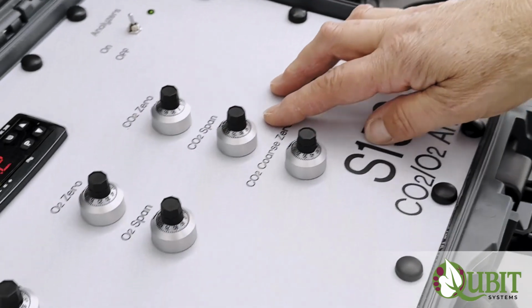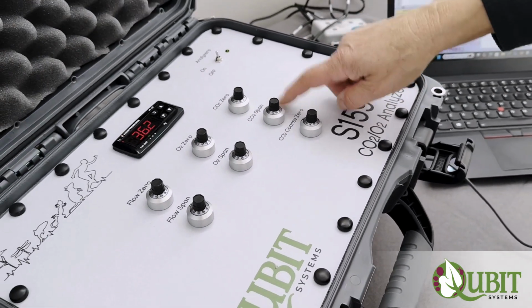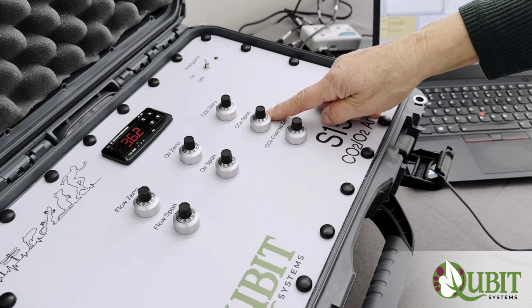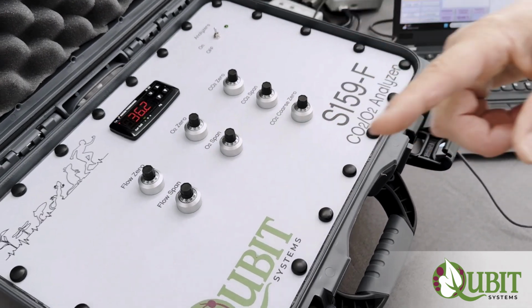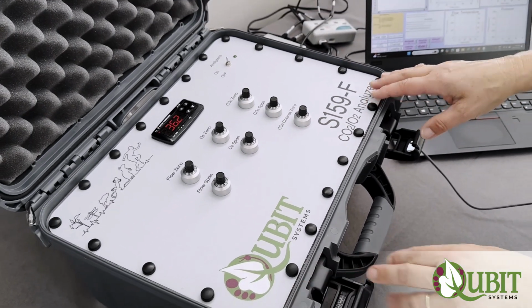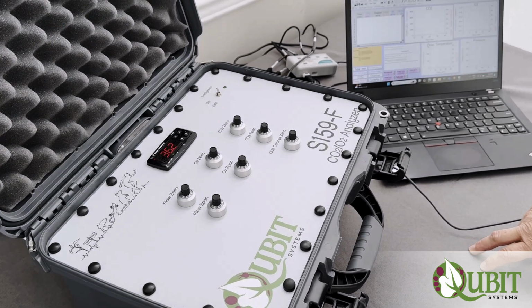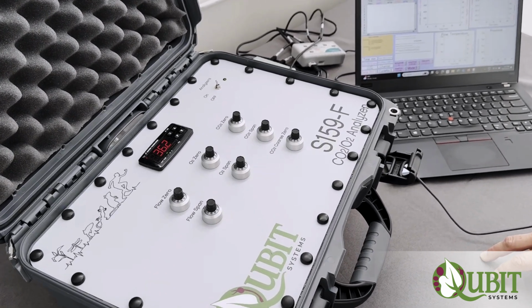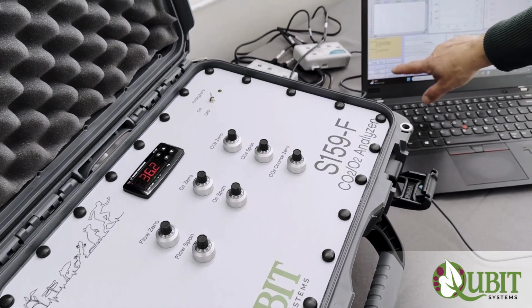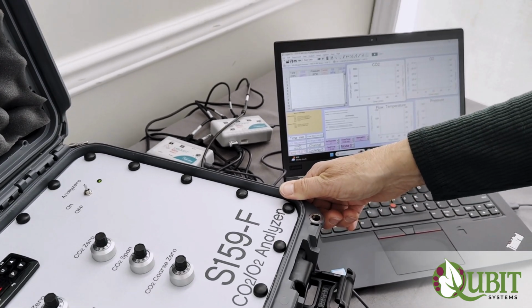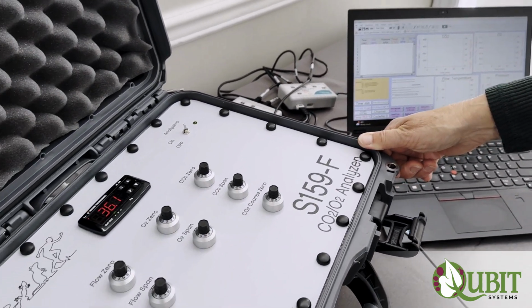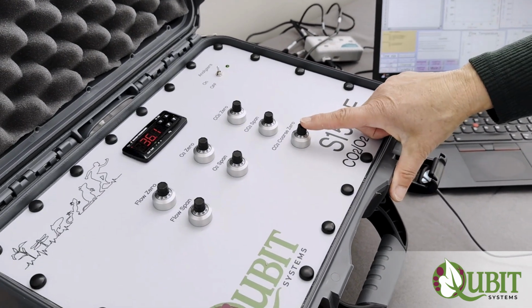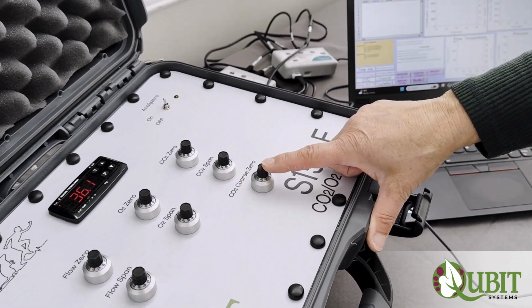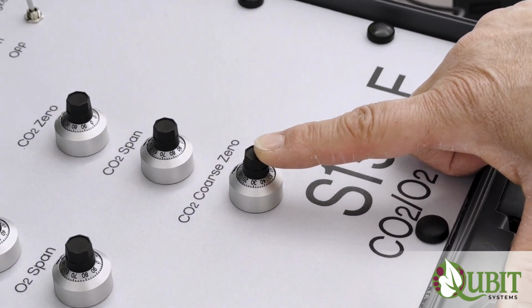505, and then you'd lock it in. If you had to do a big adjustment of CO2 span, it's a good idea to go back to 0. So disconnect the bag, connect your soda lime line, and check 0 again. If the reading for 0 is very much different, by about 40-50 parts per million, you may need to use coarse 0. Coarse 0 adjusts CO2 0.